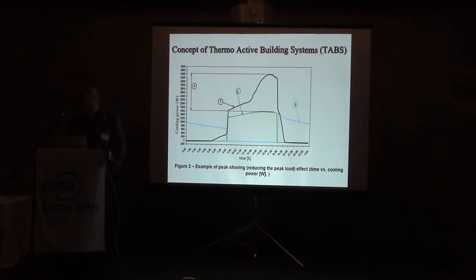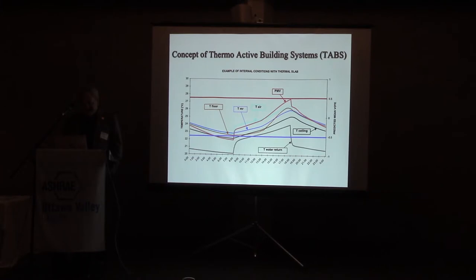And as I said, the temperatures during the day, if we have a comfort range, the trick is then to show that you will float or drift within the comfort range. And normally when we use European standard or ASHRAE it is somewhere between 23 to 26 degrees. And we have done studies and that doesn't deteriorate people's comfort. It's fully acceptable as long as you live in that level.